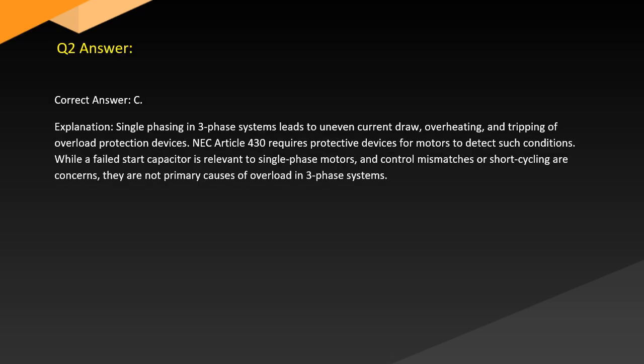Answer. Correct answer C. Explanation. Single phasing in three-phase systems leads to uneven current draw, overheating, and tripping of overload protection devices. NEC Article 430 requires protective devices for motors to detect such conditions, while a failed start capacitor is relevant to single-phase motors, and control mismatches or short cycling are concerns. They are not primary causes of overload in three-phase systems.